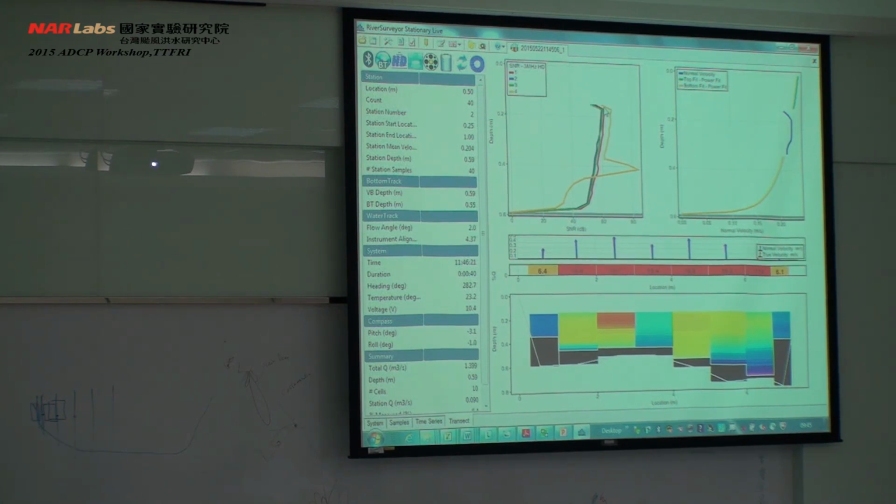The big change will come if all of a sudden they separate massively, particularly where it's leaving the instrument, and that would normally be aeration. It could be that some debris has got stuck on the transducer, a leaf or something, blocking it slightly and absorbing some of that sound. That's beam number one before, and that's beam four. So it's not aeration at all. It's one of the side things.